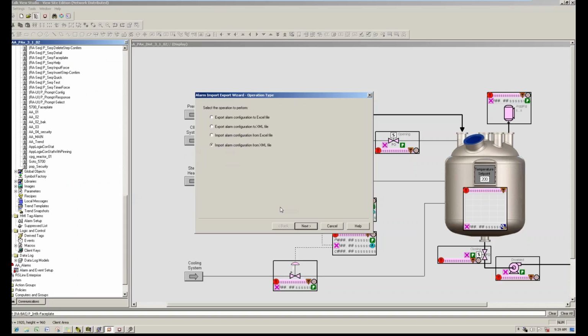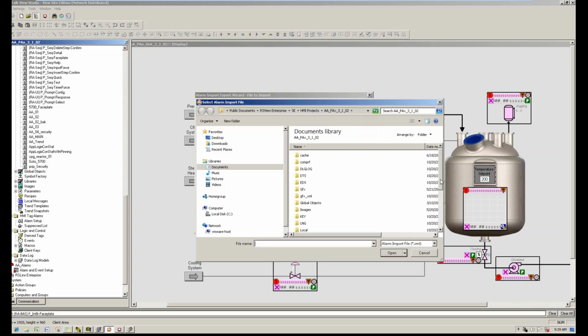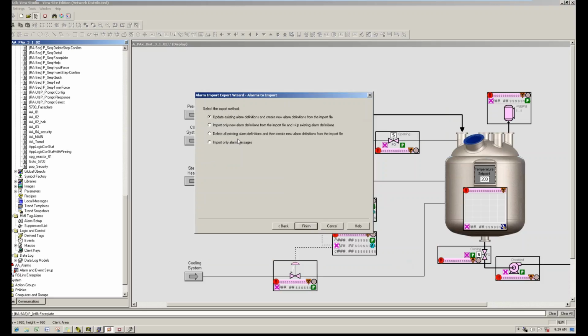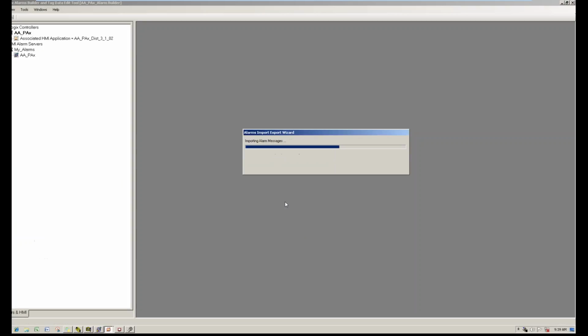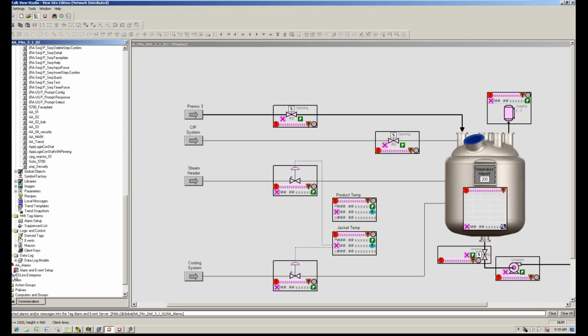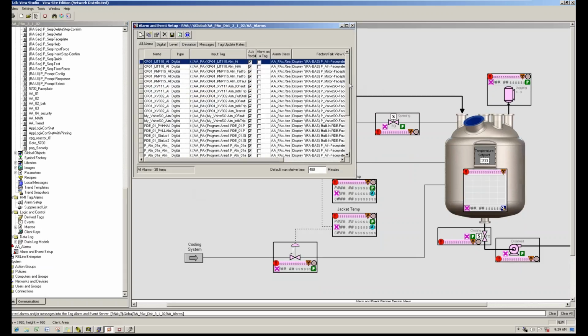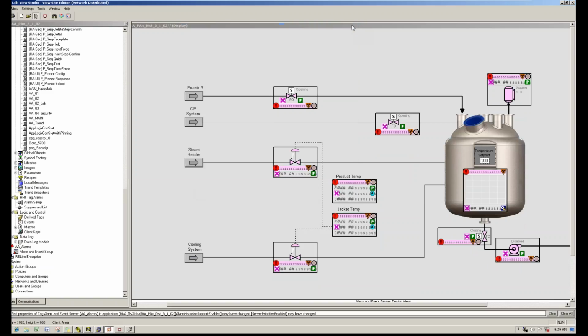And I'm going to import an XML file. I browse to the same location, select the file I've just created, and I've got an option here to update existing messages, delete existing messages, and in this case I haven't got any alarms, so it's not really going to matter which one I select. But it just goes through there and import has completed, and what that has done in my scenario has created 30 alarms. So it's created those 30 alarms in my system.